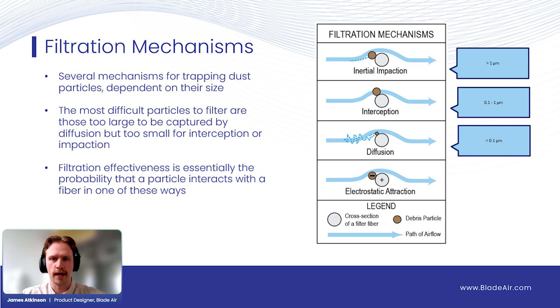So you think, if I need better filtration, I just have to increase the probability that one of these particles is trapped. All these different methods of capture really rely on the dust particle coming into close contact with the filter fiber, so to achieve better filtration you have to pack those fibers closer together. That also means your air paths are smaller, so you get more air pressure drop across the filter as you pack the fibers closer together.